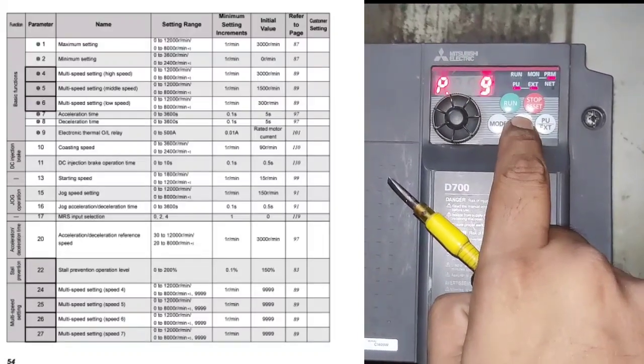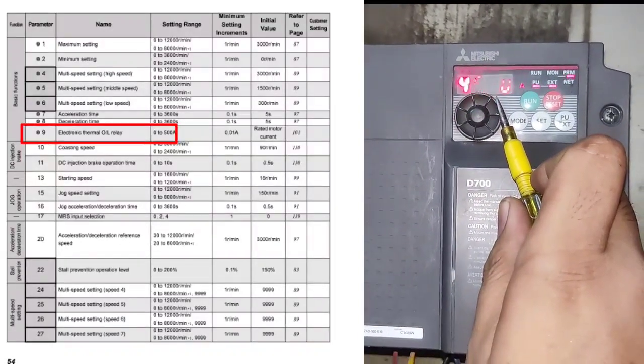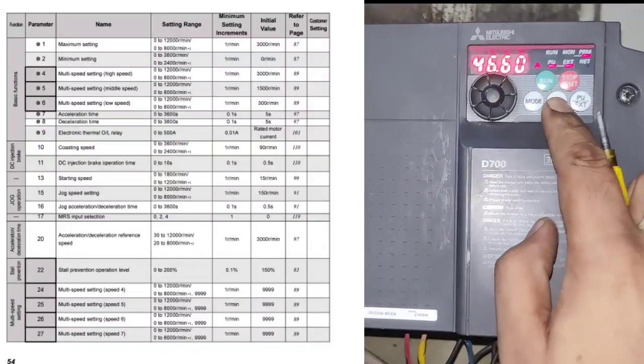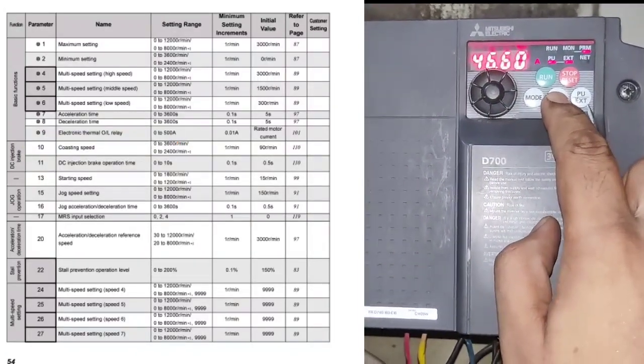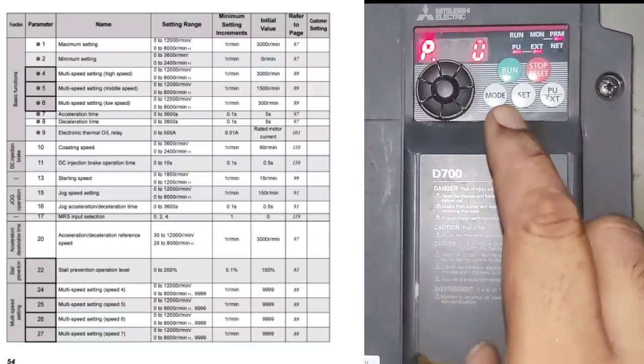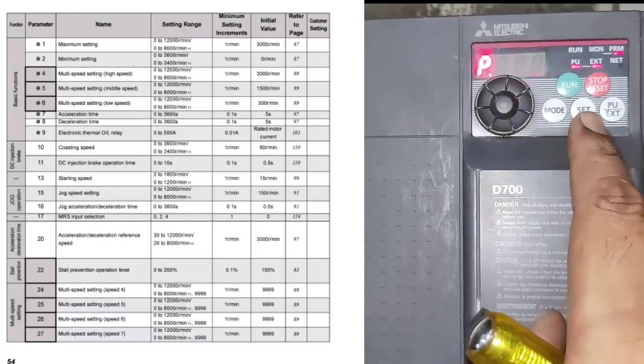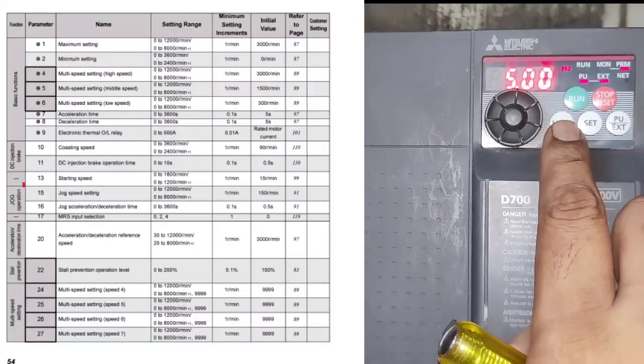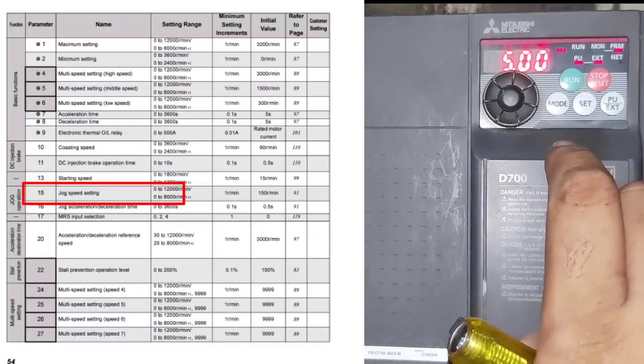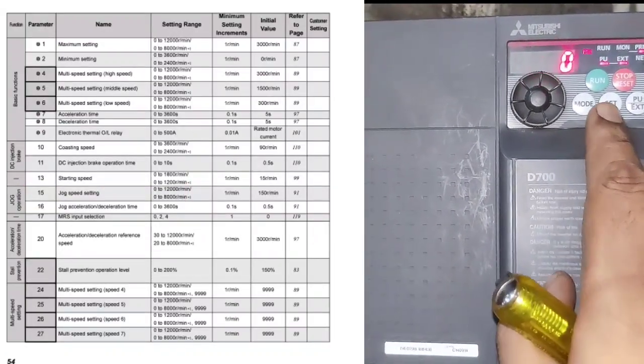Next parameter is P9, which is overload setting or electronic thermal overload relay — set the overload ampere value of your motor here. Next is P15, which is for jog frequency. We set 5 Hz for jog frequency. When you inch your drive, 5 Hz is set for jog application.